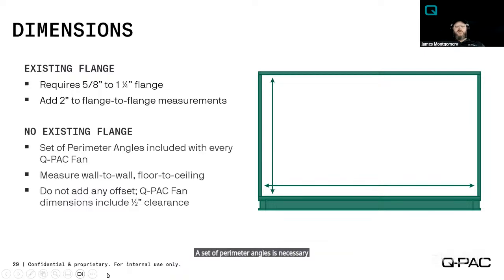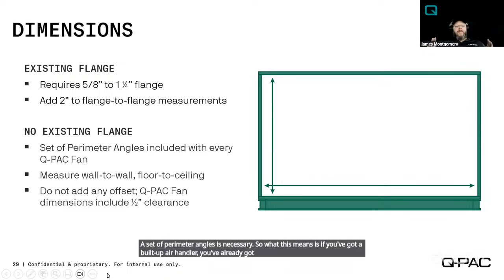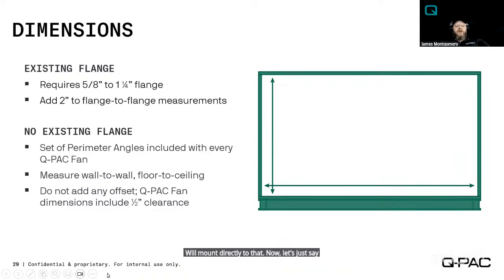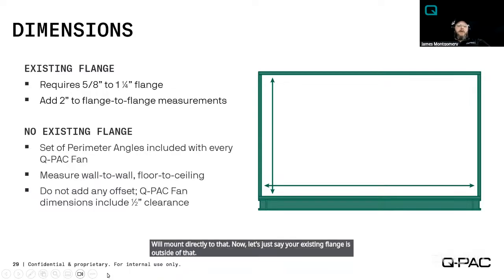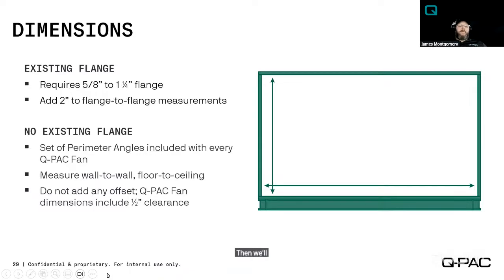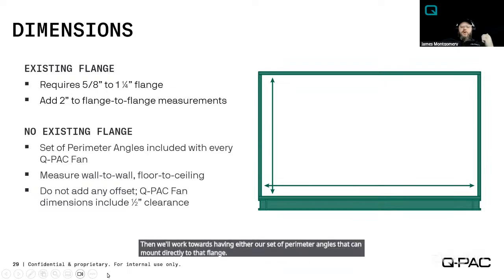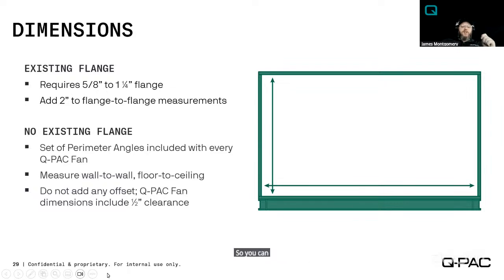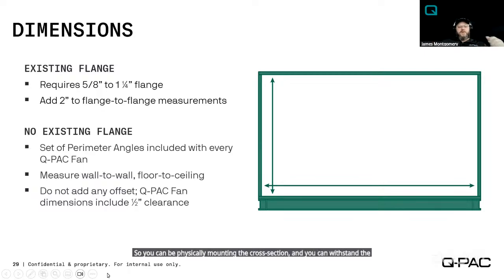So what this means is, if you've got a built-up air handler, if you've already got a custom air handler, and there is an existing flange, we'll mount directly to that. Now, let's just say your existing flange is outside of that, then we'll work towards having either our set of perimeter angles that can mount directly to that flange, so you can be physically mounted in the cross section and you can withstand the forces that this system is going to provide.